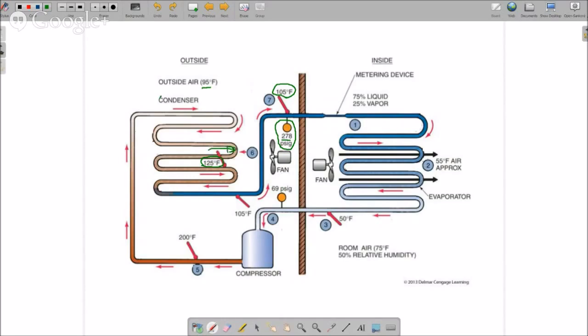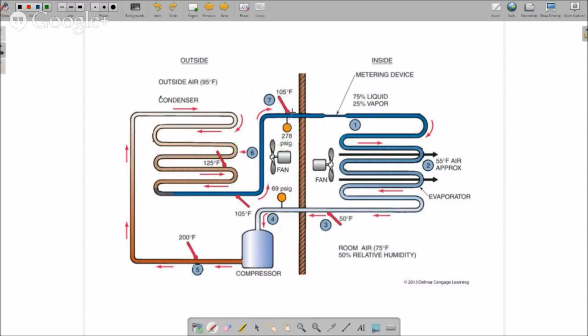You're looking at what's happening here in the center of the condensing coil. You're not looking at what's happening here where your gauge is connected. So what you're doing is your gauge tells you the saturation temperature and pressure of the refrigerant in the middle of the condensing coil, and then your thermometer tells you what the temperature actually is after it's been subcooled.